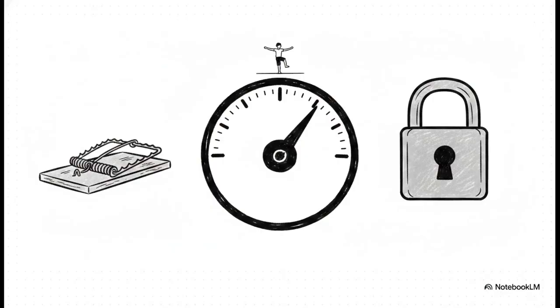The crucial takeaway here is that you genuinely cannot maximize both simultaneously. It's like a dial. If you crank that dial all the way to maximum dependability, your system gets so sensitive it'll trip at the slightest voltage dip. There goes your security. Turn it to maximum security, the system becomes so stubborn it might ignore a real fault. Every relay setting and every scheme design is a deliberate trade-off tuned to what's more costly in that specific application.